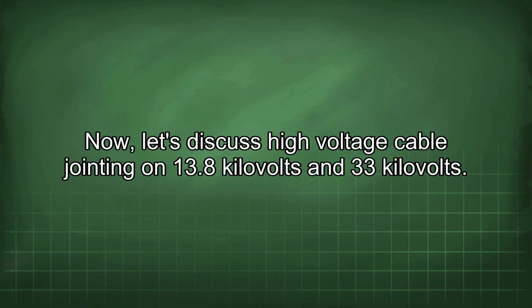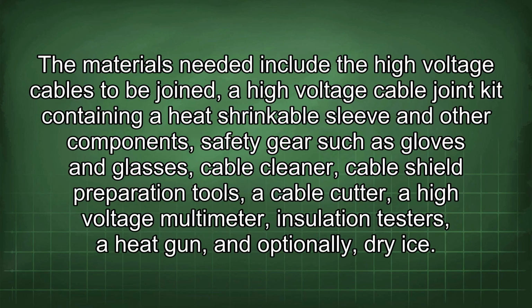Now let's discuss high voltage cable jointing on 13.8 kilovolts and 33 kilovolts. The materials needed include the high voltage cables to be joined, a high voltage cable joint kit containing a heat shrinkable sleeve and other components, safety gear such as gloves and glasses, cable cleaner, cable shield preparation tools, a cable cutter, a high voltage multimeter, insulation testers, a heat gun, and optionally, dry ice.